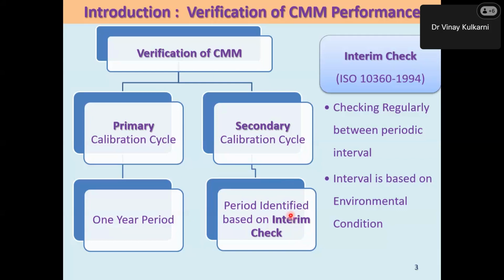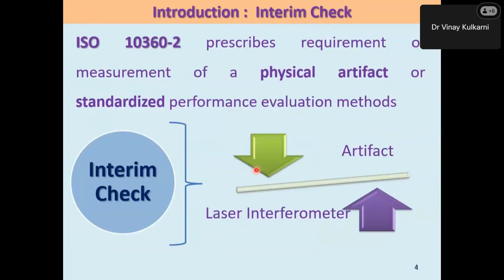and this error will keep creeping inside the system, because CMM is a system. It's not just a measuring device or a measurement machine. It's an entire system that picks up the coordinates, then goes for the computerization and then checks out the results. So for verification of CMM, we always need to check regularly between two periodic intervals. Any two periodic intervals, we can check. The interval is based on the environmental condition. That is very important, so we have to keep the environmental condition ready also.